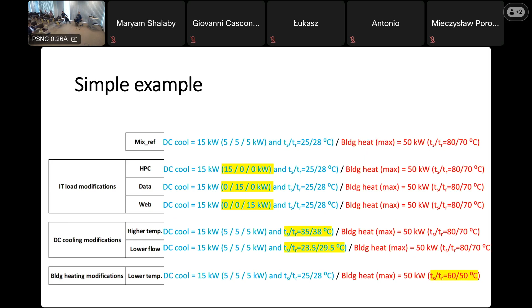So what are the results? We have cooling needs, heating needs, electricity for the heat pump, and remaining cooling and heating needs which we have to cover by other systems. Usually these two values are the same, like in the reference case. Only in the IT load modification case are they different, because we're changing the task composition, so we get different cooling needs. But there are differences only in some cases.